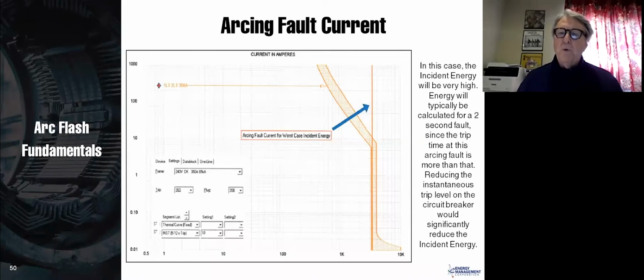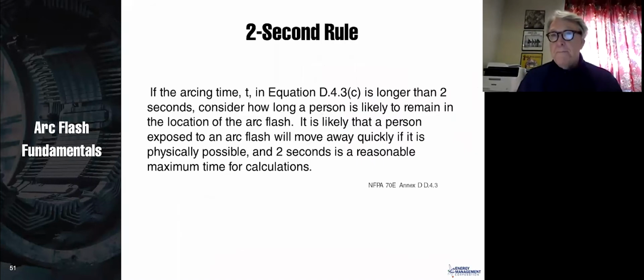So whenever we see this, we want to be careful about, is there any way that we can reduce that instantaneous trip to get it under the arcing fault current? Here's the 2-second rule from NFPA 70E. If the arcing time in equation D4.3 C is longer than 2 seconds, consider how long a person is likely to remain in the location of the arc flash.